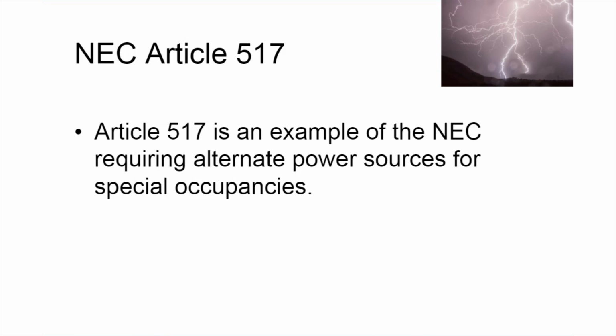So let's talk about Article 517, healthcare facilities. When you dig into 517, it continues our theme of complex and oft-confusing ways that codes are intertwined. This code must be closely reviewed in relationship to NFPA 99, which we're not even talking about today, which is the Healthcare Facilities Code. There's a lot of things within those that play off each other. And Article 517 also steps deeper into the way the EPSS are defined and discussed. Here they use the term alternate power source. So we talk about EPSS in all the other codes, but now we're looking at what's an alternate power source.